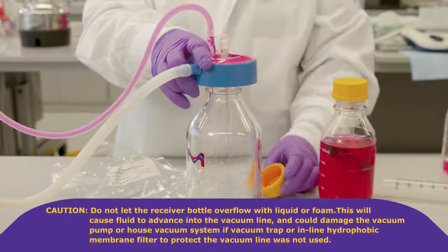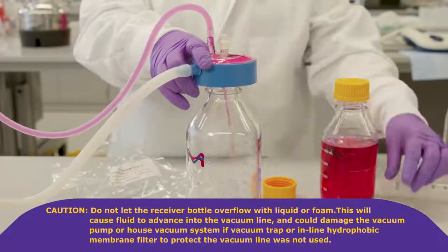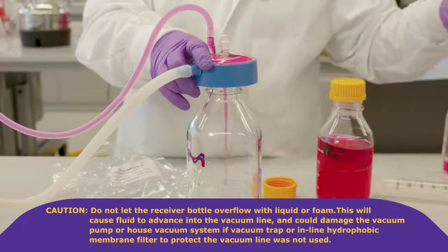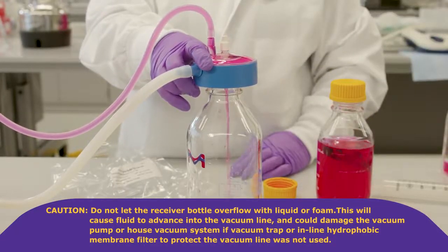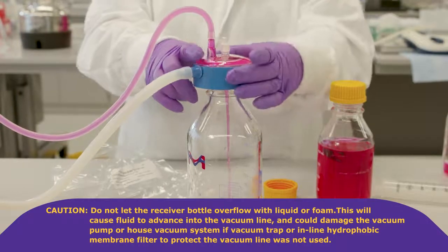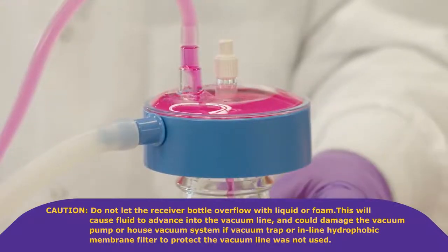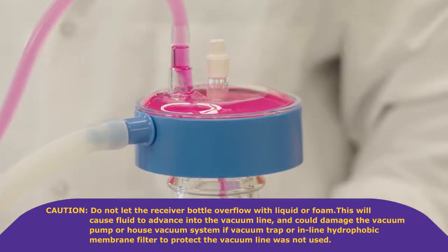Caution: Do not let the receiver bottle overflow with liquid or foam. This will cause fluid to advance into the vacuum line and could damage the vacuum pump or house vacuum system if a vacuum trap or in-line hydrophobic membrane filter to protect the vacuum line was not used.